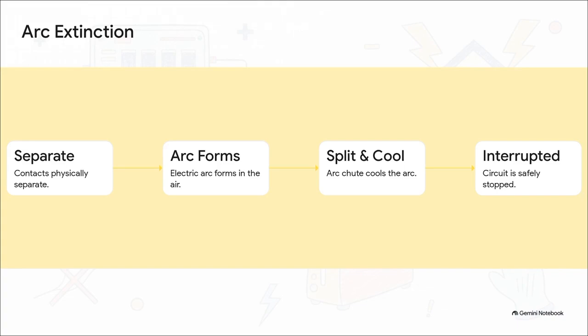Well, let's walk through this absolutely brilliant 4-step sequence, which, by the way, all happens in a mere fraction of a second. Step 1, the breaker detects the fault and the internal contacts violently separate. Step 2, the electricity fights back and a fiery arc forms right in the air between those separated contacts. Step 3, okay, this is where the real magic happens. The breaker uses an arc extinguishing system called an arc chute. This ingenious device literally forces the arc into a series of metal plates that split the arc into smaller pieces and rapidly cool it down. And finally, step 4, the arc is fully starved and extinguished. Only then is the circuit safely and truly interrupted.